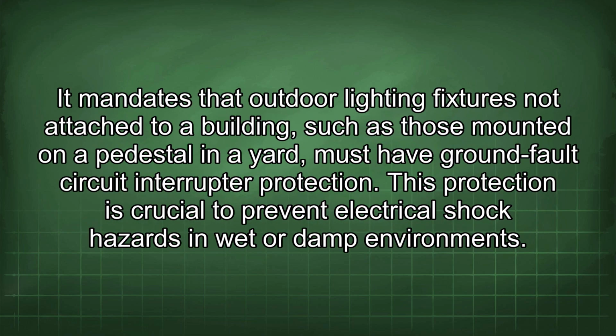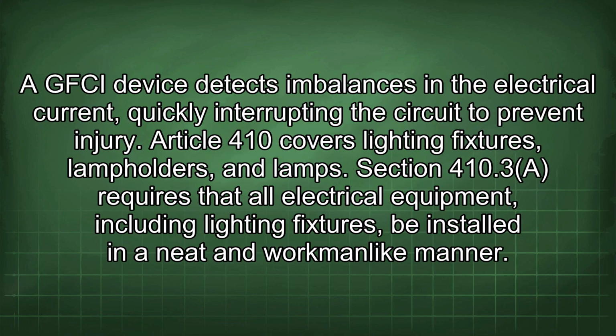It mandates that outdoor lighting fixtures not attached to a building, such as those mounted on a pedestal in a yard, must have ground fault circuit interrupter protection. This protection is crucial to prevent electrical shock hazards in wet or damp environments. A GFCI device detects imbalances in the electrical current, quickly interrupting the circuit to prevent injury.